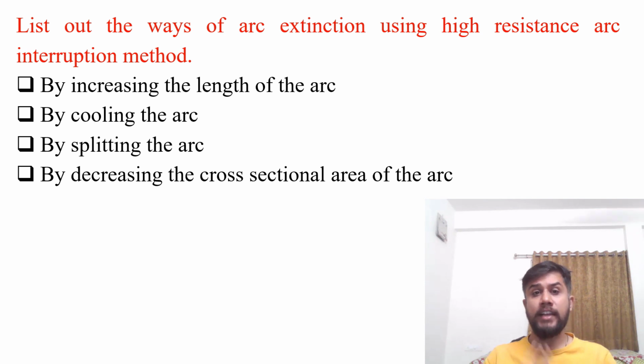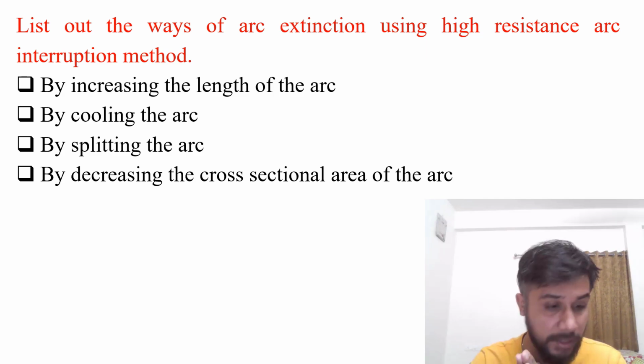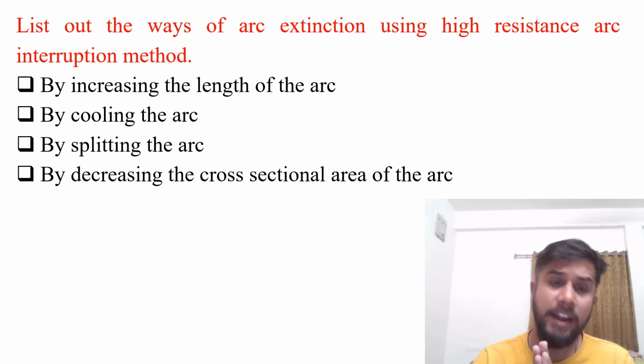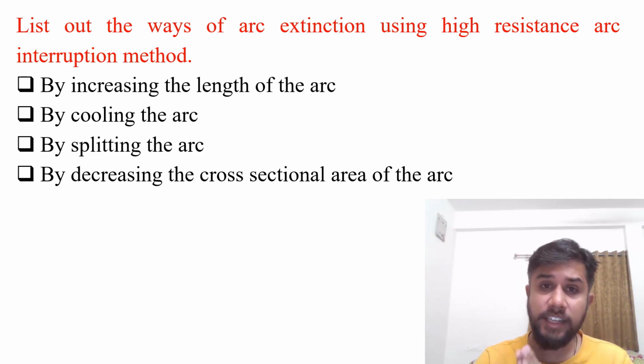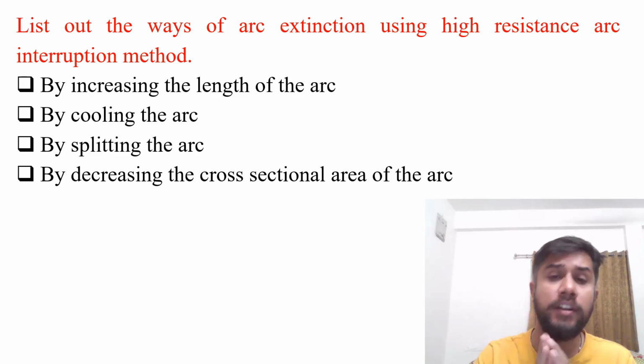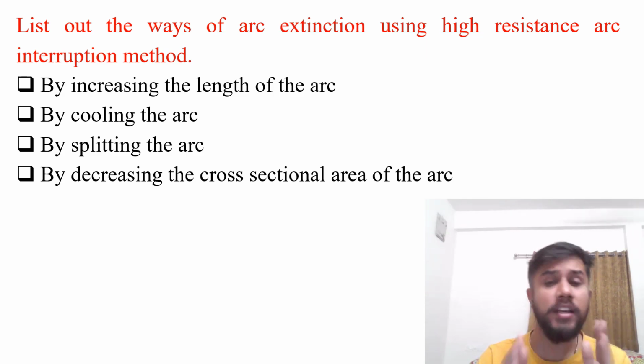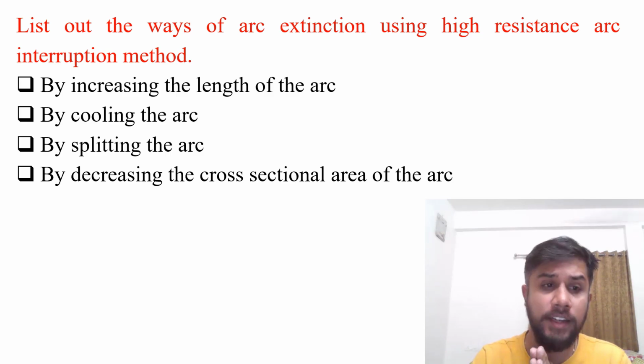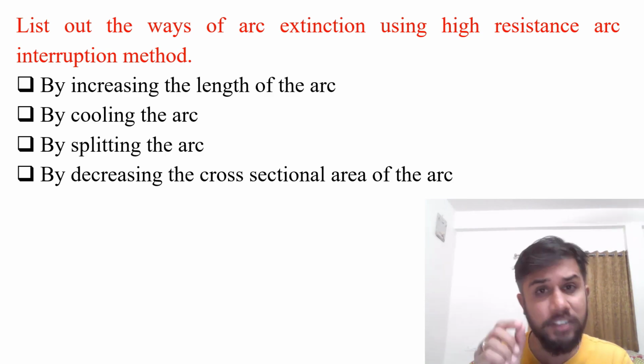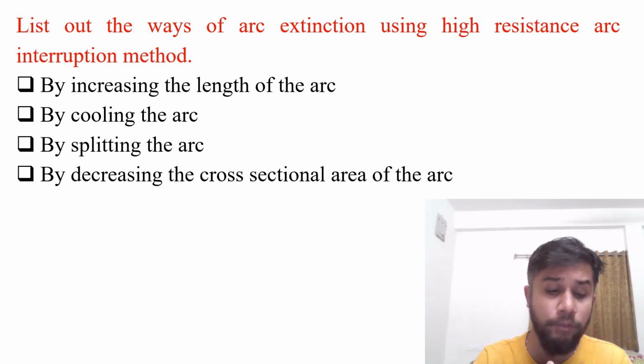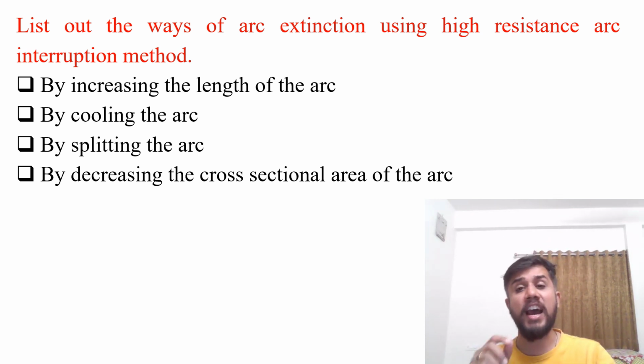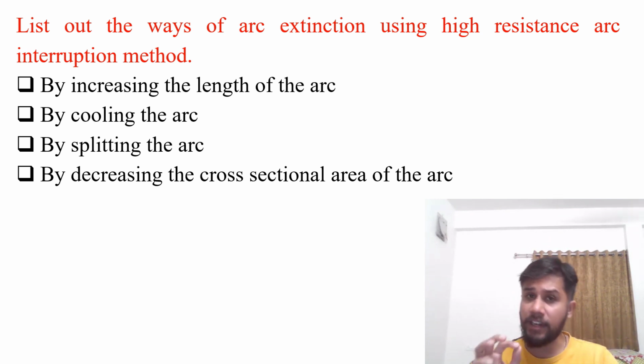List out the ways of arc extinction using the high resistance arc interruption method. There are mainly four ways. First is by increasing the length of the arc. Second is cooling, that is, reducing the temperature of the arc. Third is splitting of the arc, and last is decreasing the cross-sectional area of the arc. So these are the four ways to extinguish the arc using the high resistance arc interruption method.